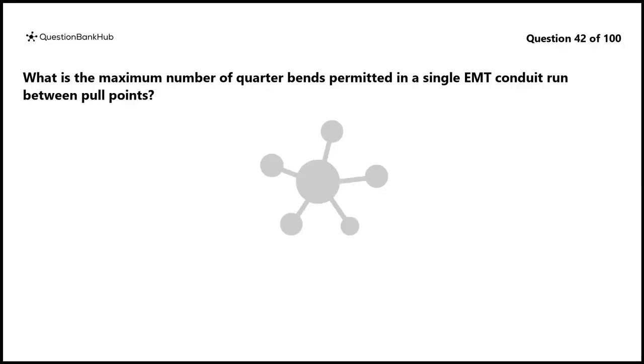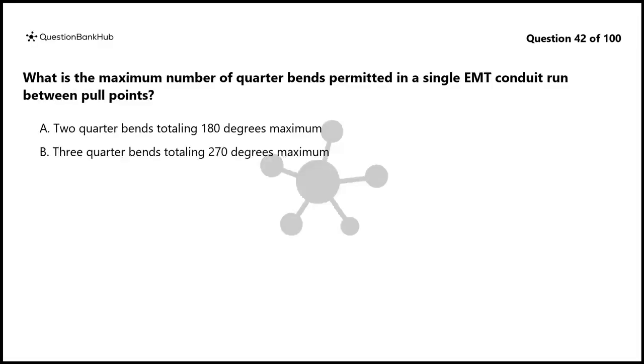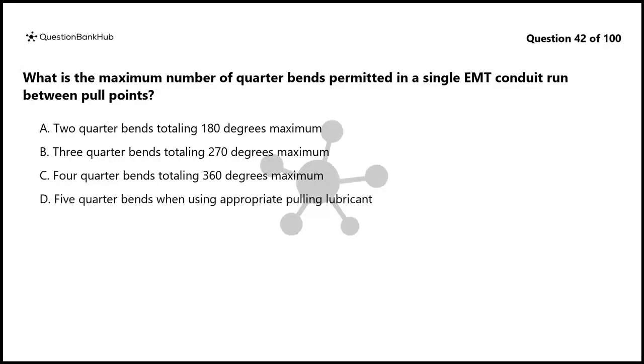Question 42. What is the maximum number of quarter bends permitted in a single EMT conduit run between pull points? A. 2 quarter bends totaling 180 degrees maximum. B. 3 quarter bends totaling 270 degrees maximum. C. 4 quarter bends totaling 360 degrees maximum. D. 5 quarter bends when using appropriate pulling lubricant.